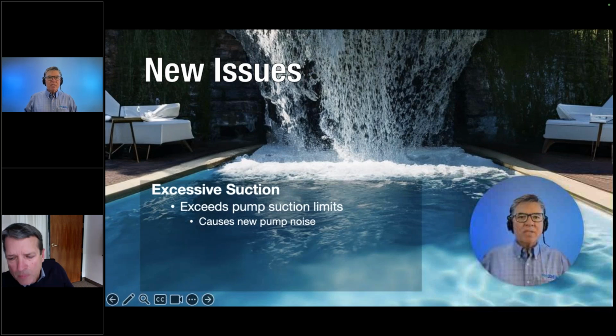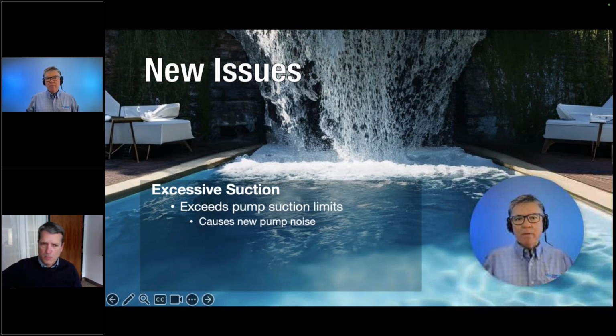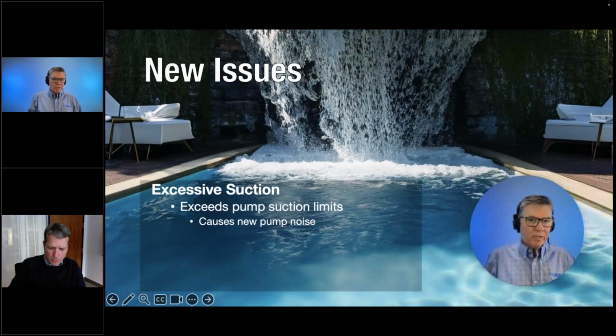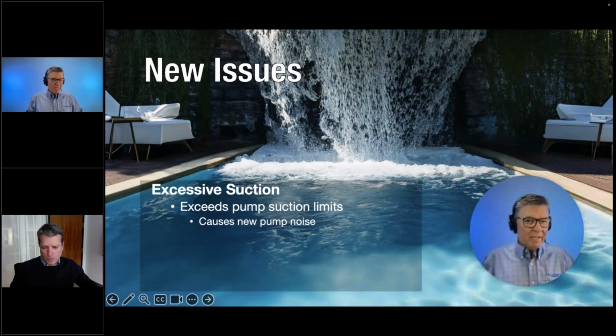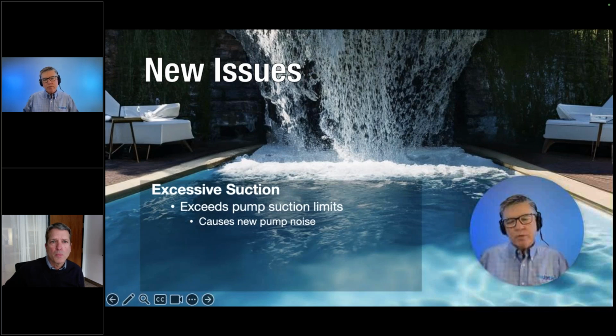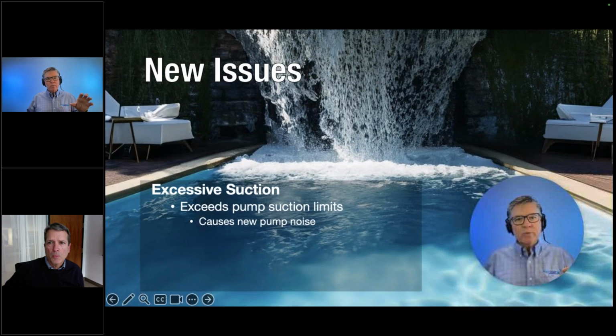And what that noise is cavitation. It may be cavitation in the pipe, and obviously we hear it at the pump, but if you get down and listen close with a big pump on small pipe, old Ortega valves, I'll use the brand because they're not around anymore, you know, little itty bitty old-fashioned valves, you'll hear them squealing because they can't handle the flow rate of these new pumps. And then certainly if you have a big modern pump and then reduce it down to 2-inch or 1.5 inch when its performance curve is based on 2.5, maybe 3-inch pipe on some of the bigger variable speed pumps that are in the residential market now. So be aware, the first clue is going to be pump noise, even after the pump's primed. And we're going to cover priming a little bit because that's kind of a gotcha sometimes also.